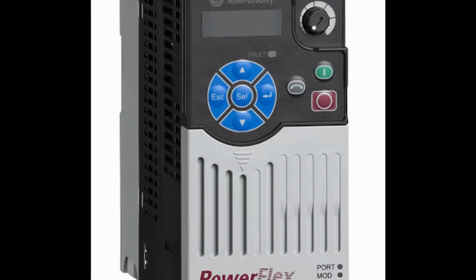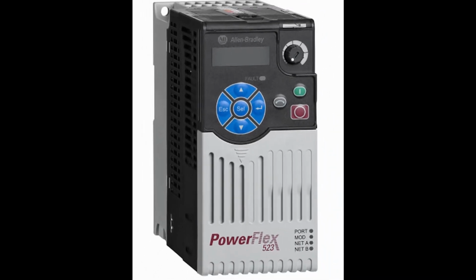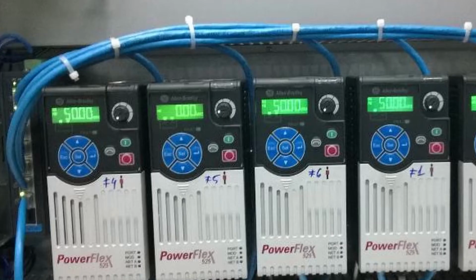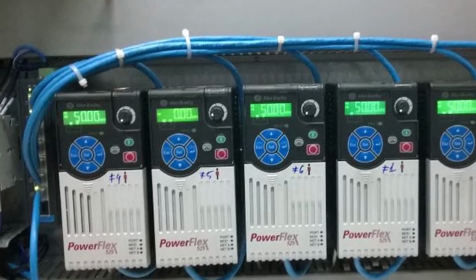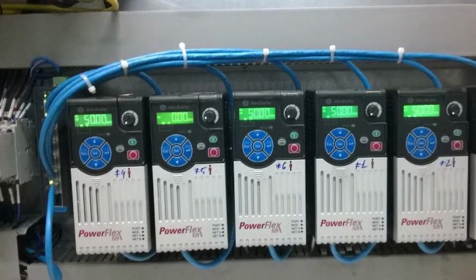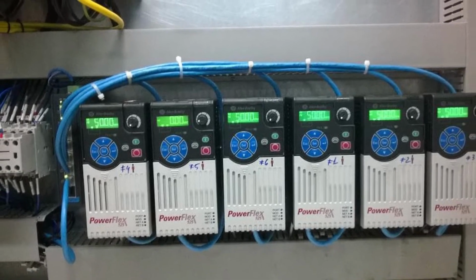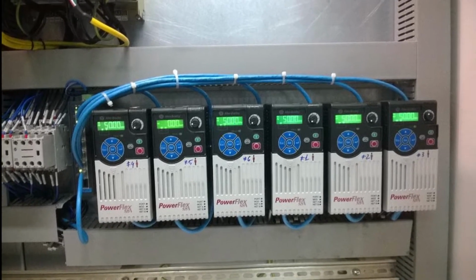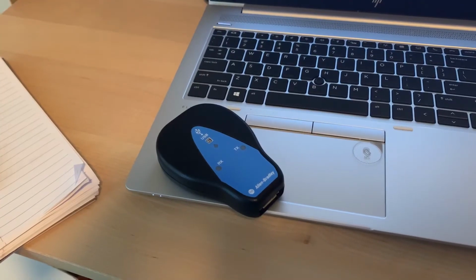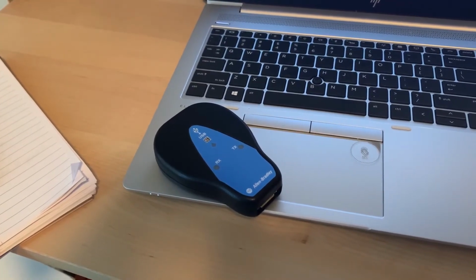Reason one, if your drive does not have an Ethernet port, then using an Ethernet cable will not work. Reason two, using a 1203 USB in conjunction with an already networked drive allows you to access drive parameters without breaking the existing network connection. And reason three, the 1203 USB acts as a fuse.